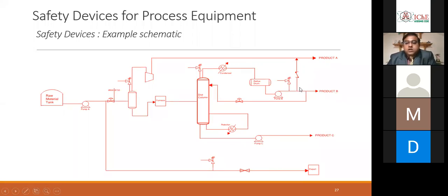So one stream of this pump goes into the compressor discharge, also gets mixed, and it's another kind of product, and there is a check valve here. So now see, when I was telling you about this pump A, this is a 600 pound rating system because it has to send it through this distance. The shutoff pressure is very high. So this side of the control valve is 600 pound rating, the system here, including this line. But here I don't need that much pressure. So I am letting down the pressure here to a pressure which is suitable for this system.